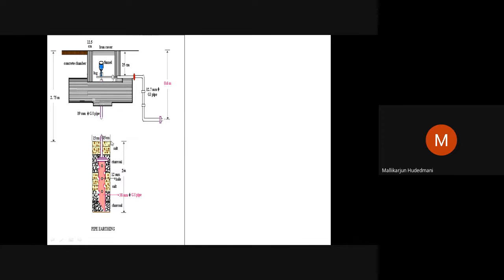You can imagine a rectangular or square cut. Centrally you insert this pipe. Imagine, then around that pipe you pour charcoal and salt as layer 1, layer 2, layer 1, layer 2 to improve the conductivity of the soil. Then this galvanized iron pipe is coupled, joined with another galvanized tube, and brought up from 2 meter deep to the earth, approximately 2.75 meter or 2 meter. This is called a cast iron or cement structure. Like the municipal corporation water taps where we have an underground mechanism, we will have a lid for that and we will have a provision.